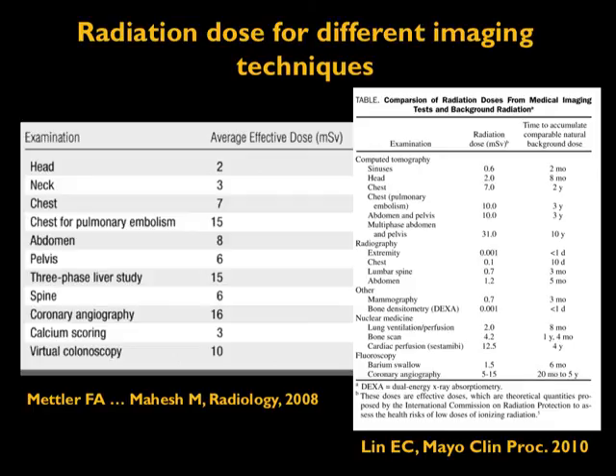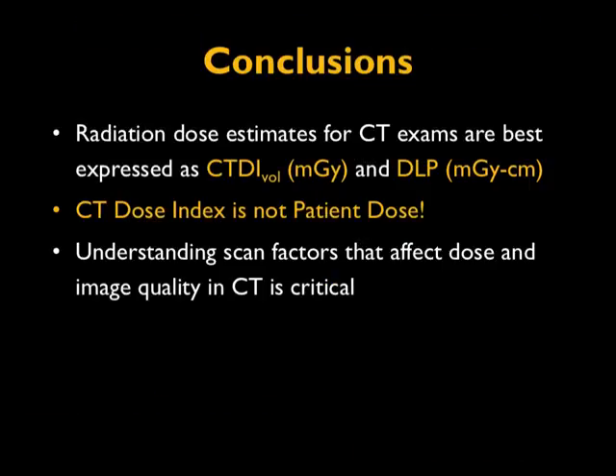For this part of the podcast, I will conclude by showing some typical radiation doses for CT protocols. These are published values showing the average effective dose for standard protocols such as head, neck, chest, abdomen, and pelvis. From the date of publication to now, some procedures can be delivered at much lower doses, but these represent the average values. In summary: radiation dose in CT is not measured directly on patients — it is based on phantom measurements. Radiation dose estimates are best expressed as CTDI vol and DLP. It is important to remember that the CT dose index is not patient dose. Understanding scan parameters and factors that affect dose and image quality in CT is critical. Thank you.